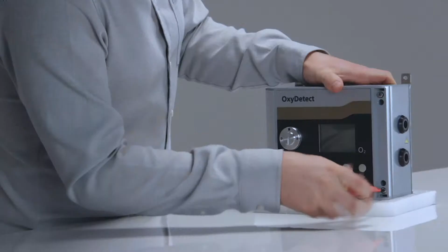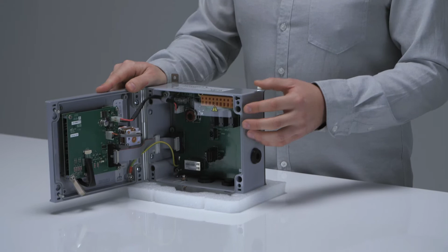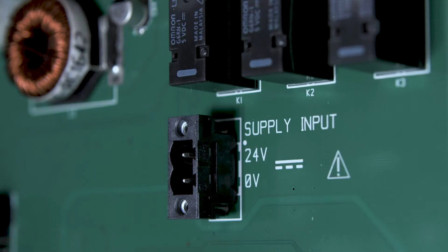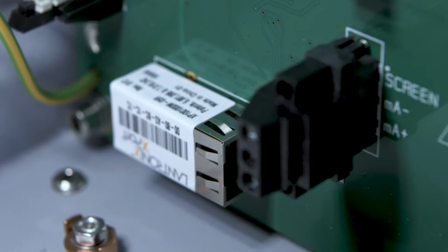So the OxyDetect can be easily wall mounted by a single person thanks to its size and weight. It can also be opened with minimal tools. So let's have a look inside. So inside we have the customer interface board, which consists of the relay outputs, and the relays are used to indicate faults and alarm conditions. We have the DC power input. We have the Modbus Ethernet output.